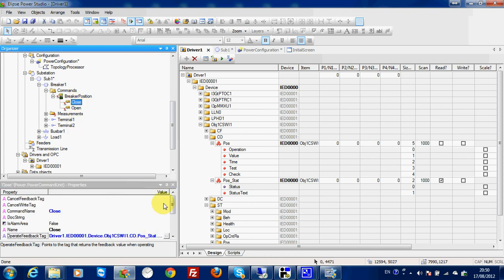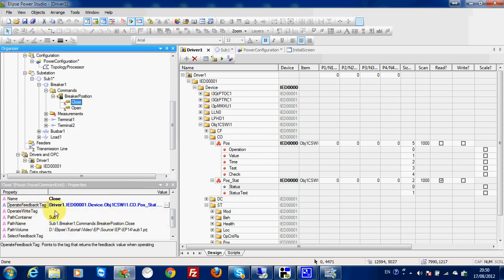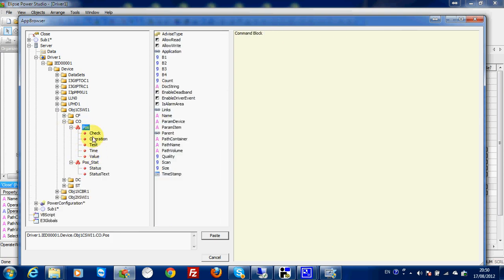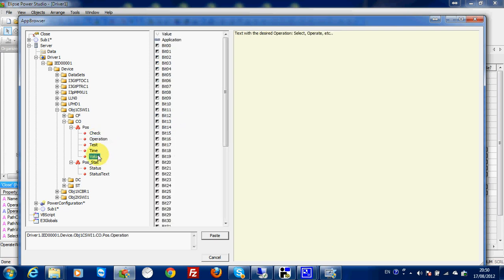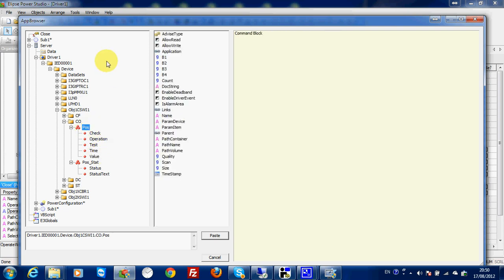Then I need to fill the tag for the operate write tag. But in IEC61850, we don't only write one tag — we have to write two tags: one is operation, one is value. So I cannot write just any tag here. I need to write a block. I will use this block to write my two tags. The only reference I can give here is just the block POS. I cannot give individual tag information because we need to write on operation and on value — so I only give the block.